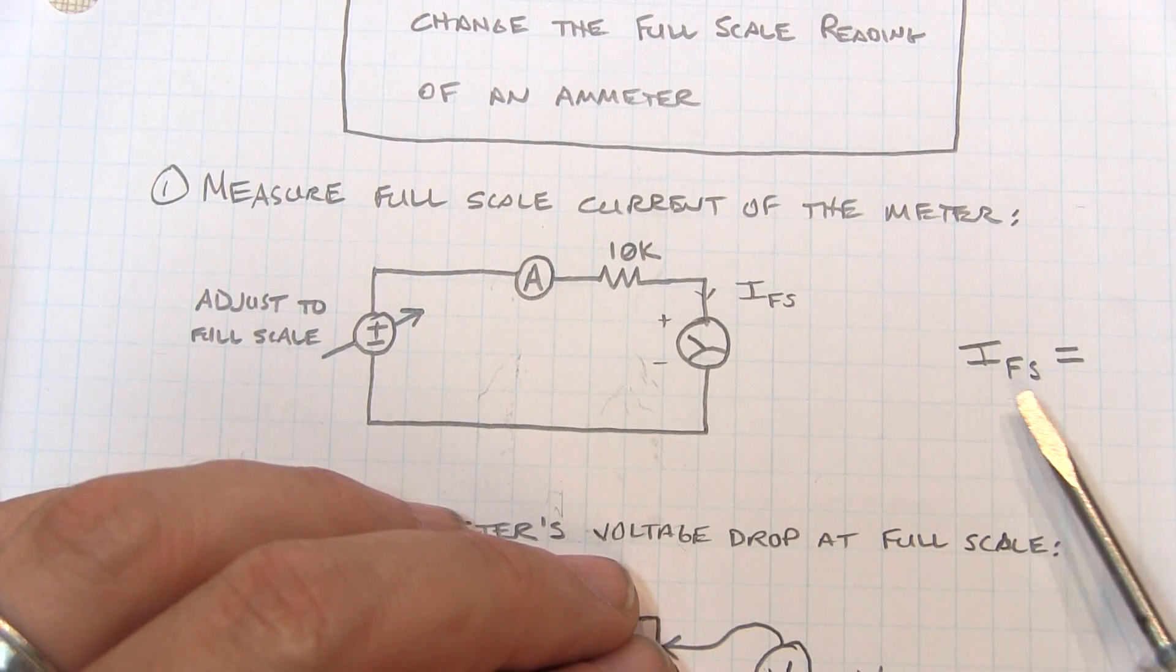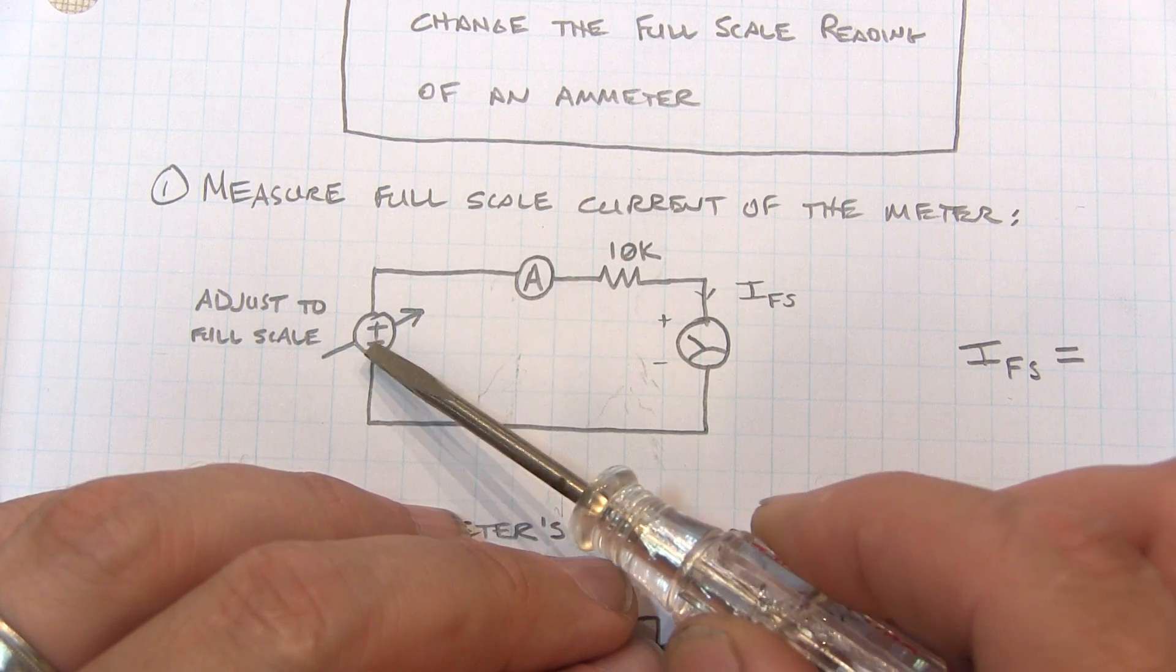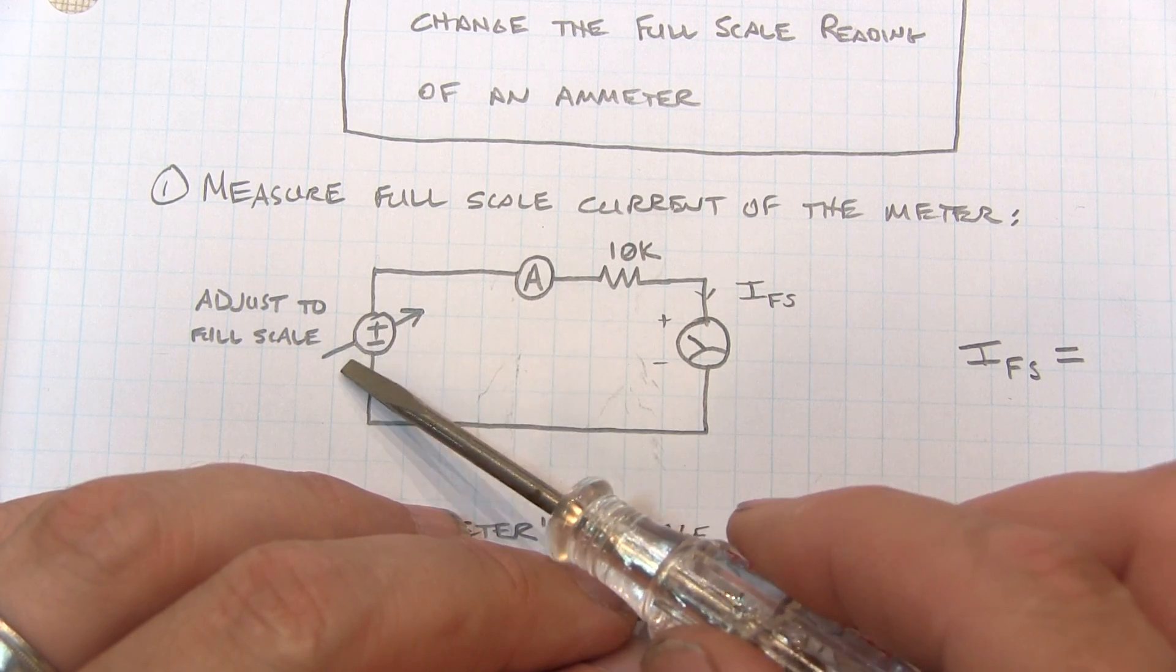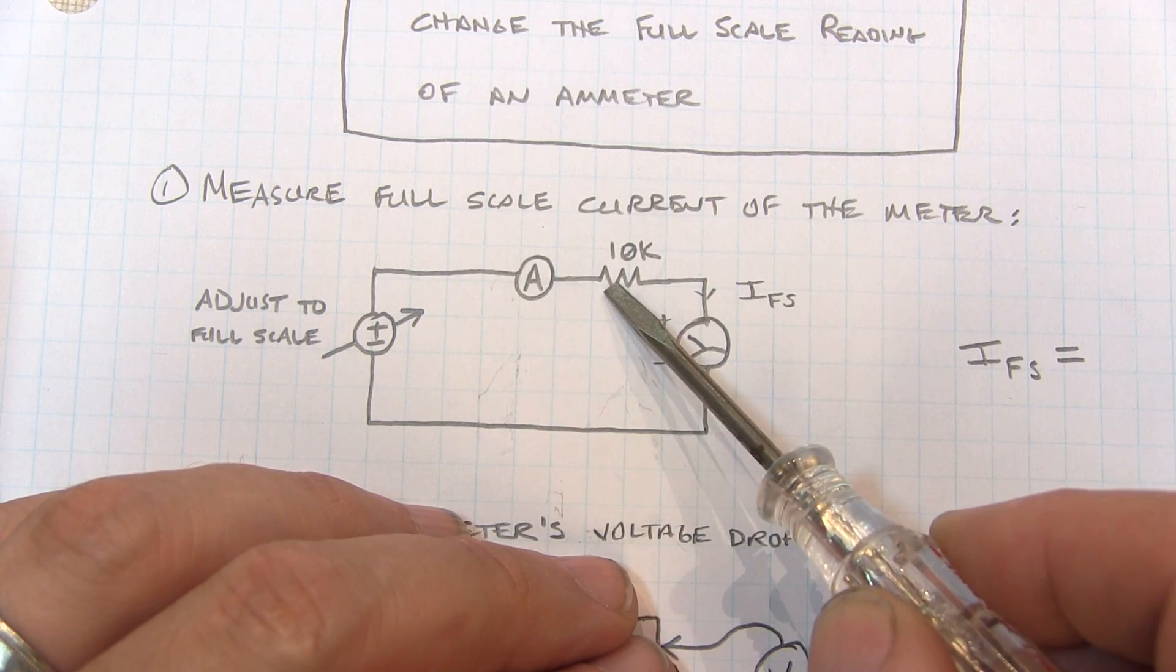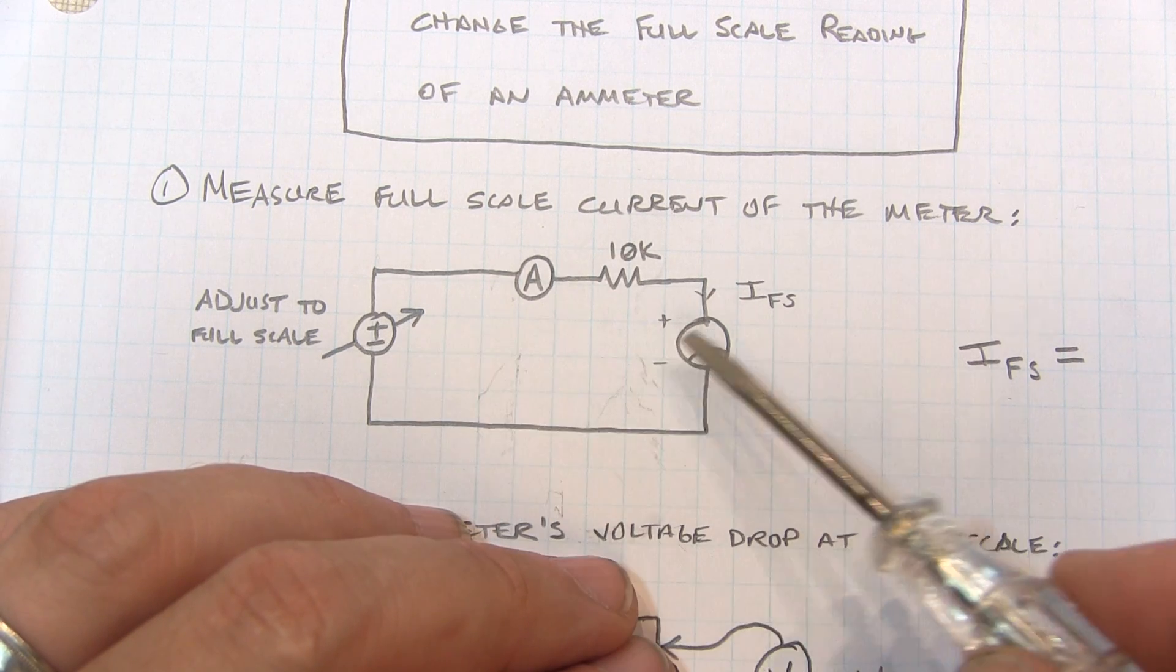So to measure the full scale current like we showed in the last video, you take a variable power supply, typically 0 to 10 or 12 volts would be sufficient, a known good ammeter in series with a 10k resistor in series with the meter that you're testing.